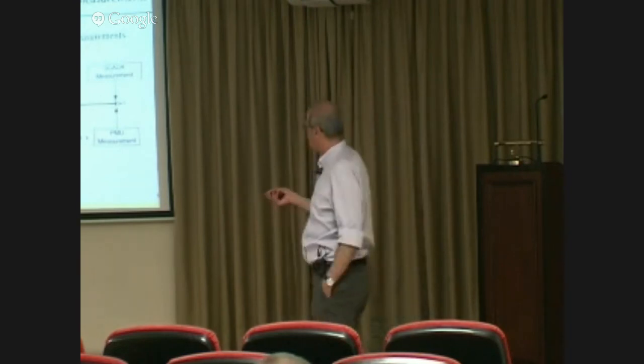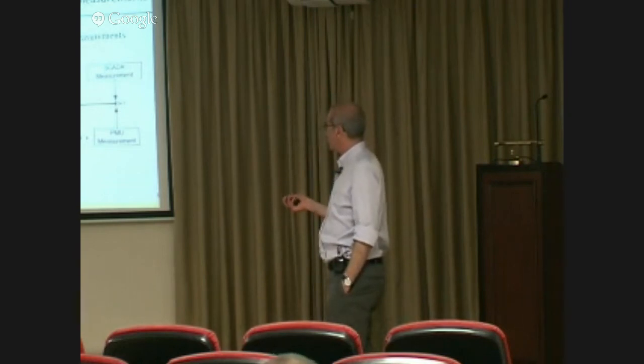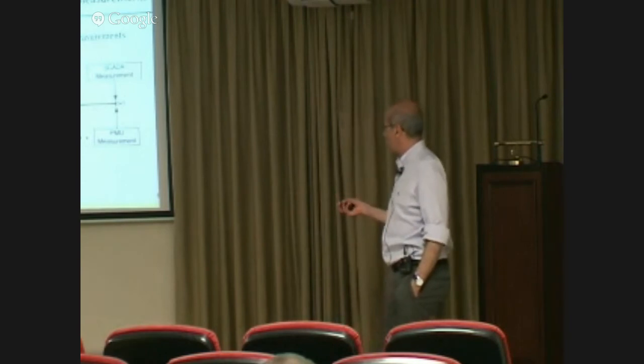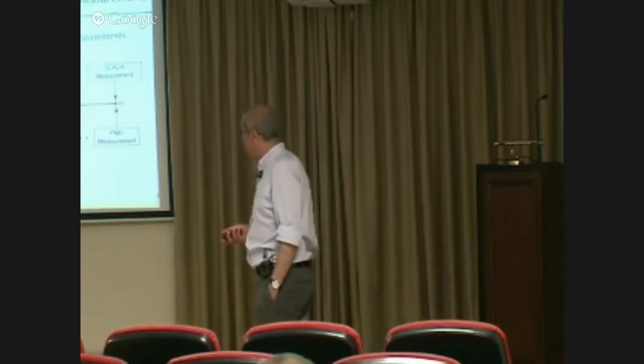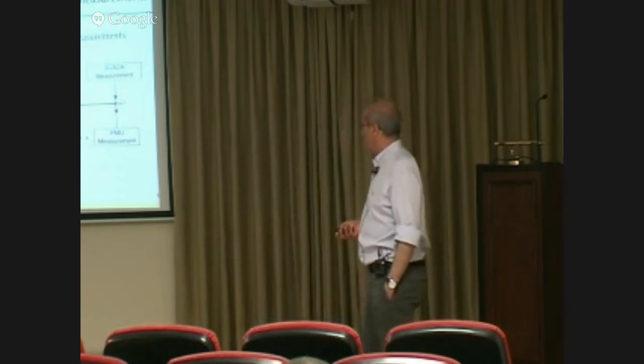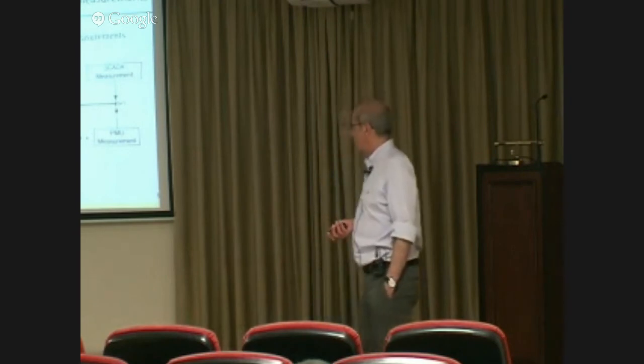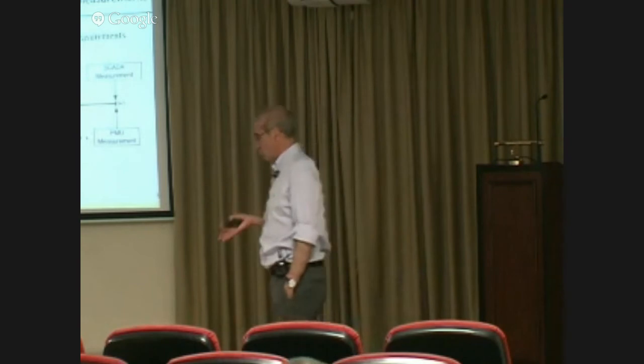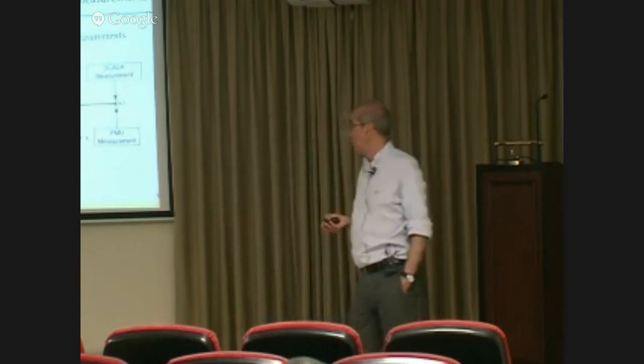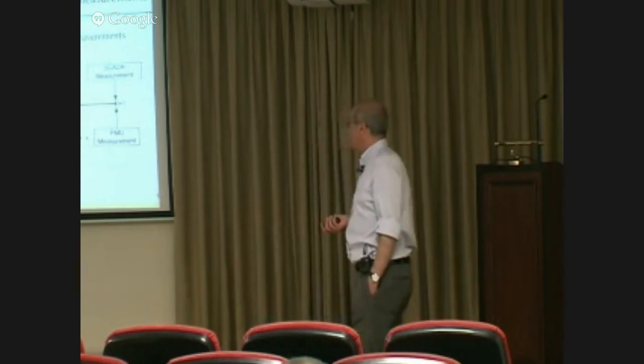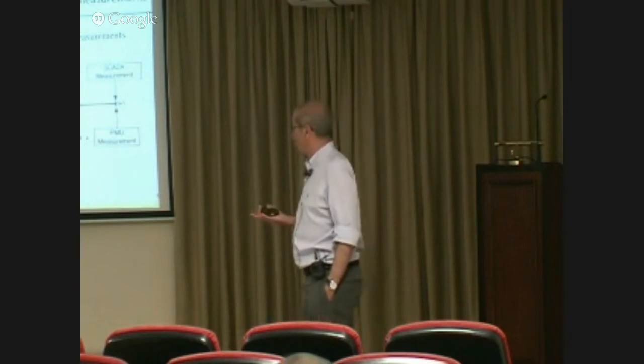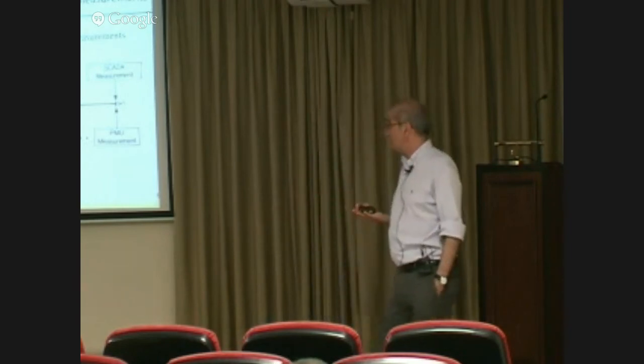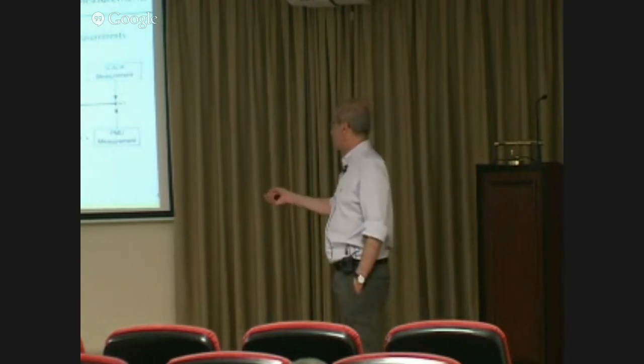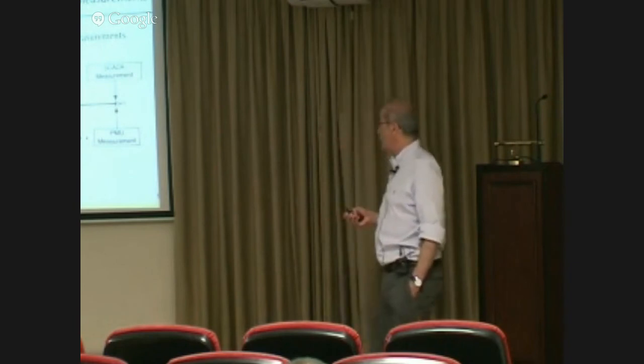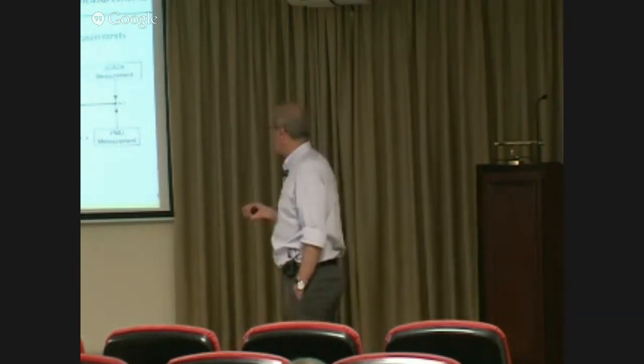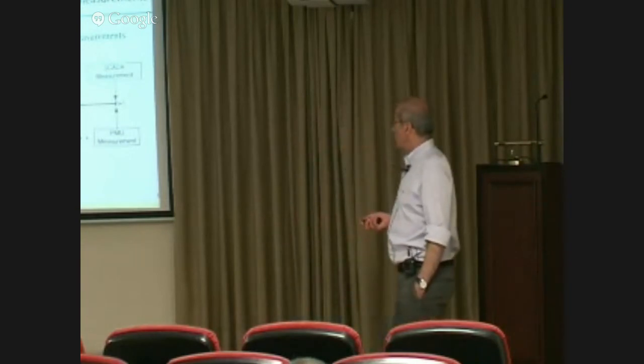The SCADA measurements, those power flows, injections and so forth, come in at a certain time, typically every 3 to 5 seconds nowadays. The state estimator itself runs at a much slower pace, maybe every 30 seconds or a minute, sometimes longer. Given that PMU measurements are available 30 to 50 times a second, between two SCADA scans every 2-3 seconds you'll receive almost 100 or more PMU measurements because of their pace.